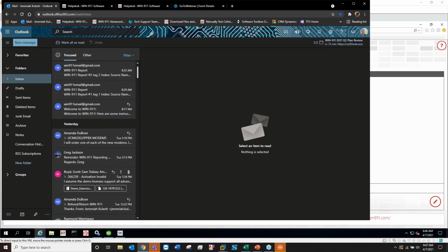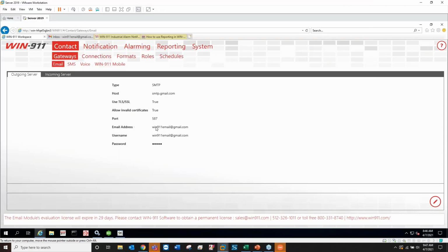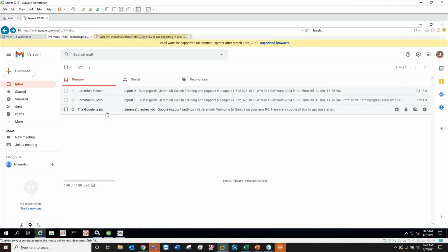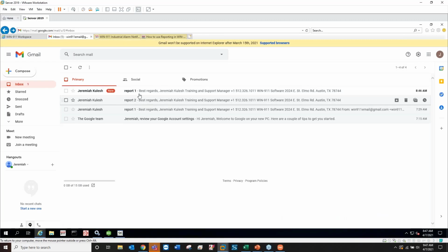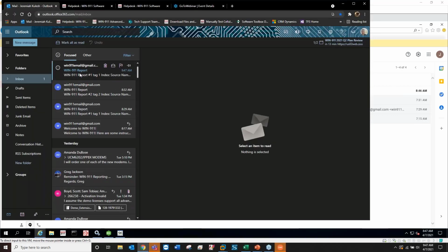So for the inbound emails, right? Because this is technically coming inbound into this WIN-911 email at gmail.com account, it takes, I think it's every 60 seconds, if I remember right, is when our WIN-911 notifier is going to poll for the new email, and there you go, and then send that report.